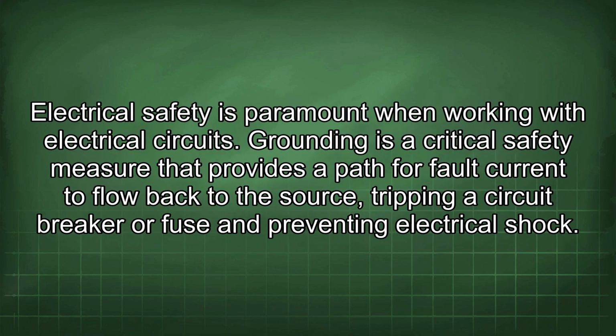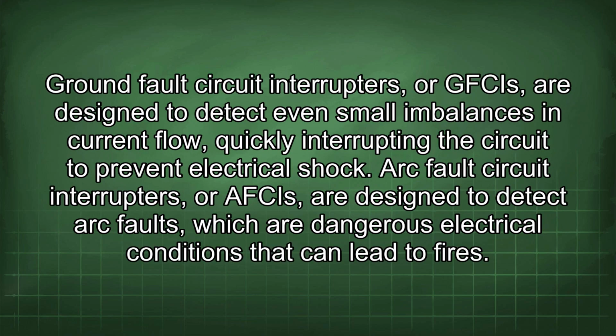Electrical safety is paramount when working with electrical circuits. Grounding is a critical safety measure that provides a path for fault current to flow back to the source, tripping a circuit breaker or fuse and preventing electrical shock. Ground fault circuit interrupters, or GFCIs, are designed to detect even small imbalances in current flow, quickly interrupting the circuit to prevent electrical shock. Arc fault circuit interrupters, or AFCIs, are designed to detect arc faults, which are dangerous electrical conditions that can lead to fires.